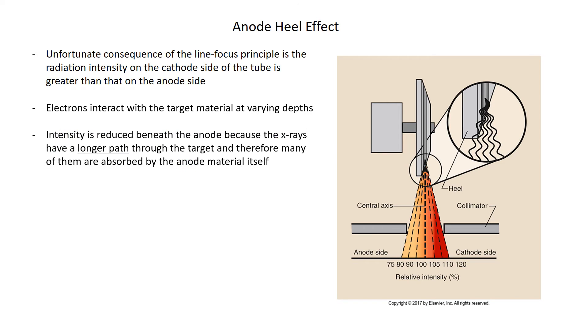The anode heel effect means that one side of your tube is going to have more intensity than the other. The radiation intensity on the cathode side of the tube is greater than on the anode side. When electrons strike the face of the anode, they interact at varying depths within the metal. The intensity is reduced beneath the anode because the x-rays have a longer path through the target and many are absorbed by the anode material. The smaller the angle, the larger the heel effect — more absorption on the anode side, less on the cathode side, giving a more intense beam on the cathode side.